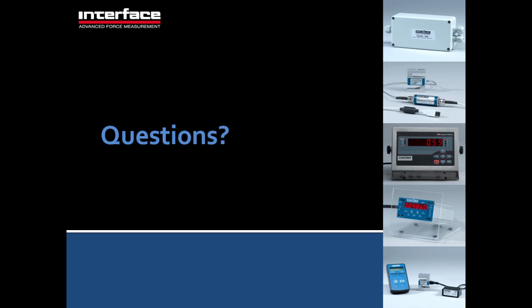How fast will the peak valley function on the 9860 respond? It'll respond immediately because, as Keith described earlier, it has a collapsible filter. So once it sees a spike in the weight change, it automatically moves to the next reading immediately. And it's limited by the display update rate of 230 samples per second.